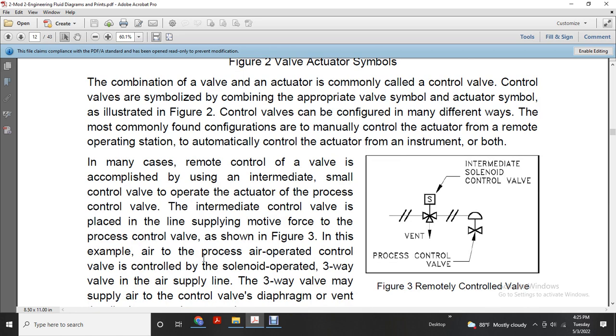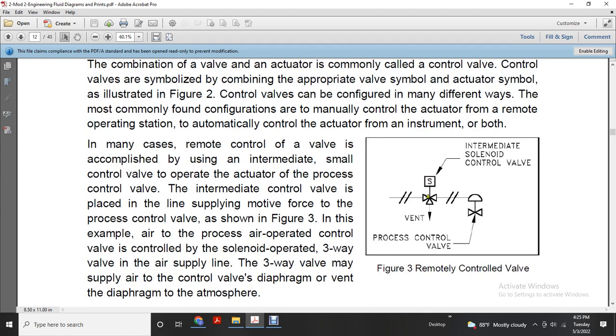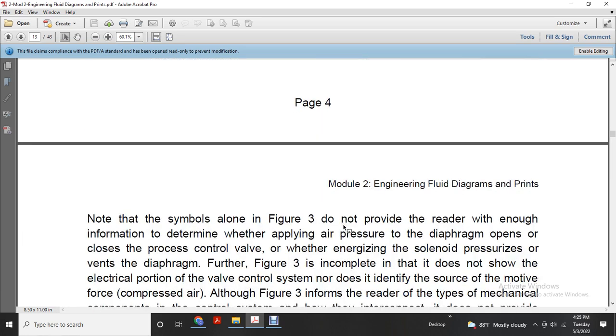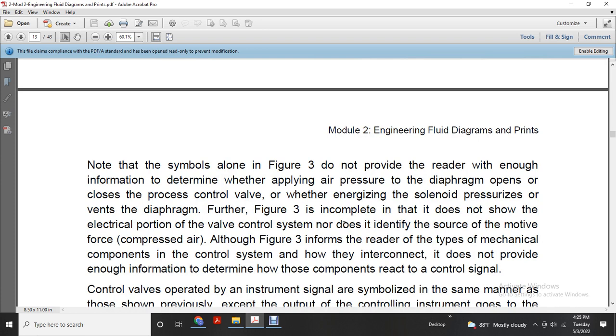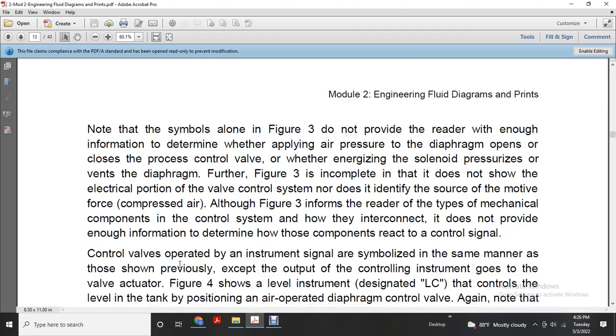In this example, the process air-operated control valve is controlled by a solenoid-operated three-way valve on an air supply line. The three-way valve may supply air to the diaphragm or vent the diaphragm. It shows the solenoid, the three-way valve, the diaphragm, and the pressure control valve. Note that the symbols alone in figure 3 do not provide the reader with enough information to determine whether applying pressure to the diaphragm opens or closes the pressure control valve, or whether the energy of the solenoid vents the diaphragm. Further, figure 3 is incomplete in that it does not show the electrical portion of the valve control system, nor does it identify the source of the motive force, compressed air. Although figure 3 informs the reader of the type of mechanical components of the control system and how they interconnect, it does not provide enough information to determine how the components react to a control signal.